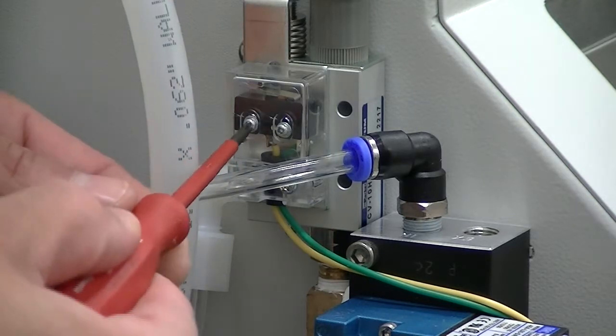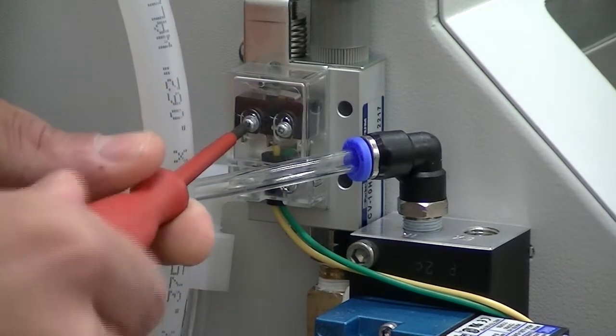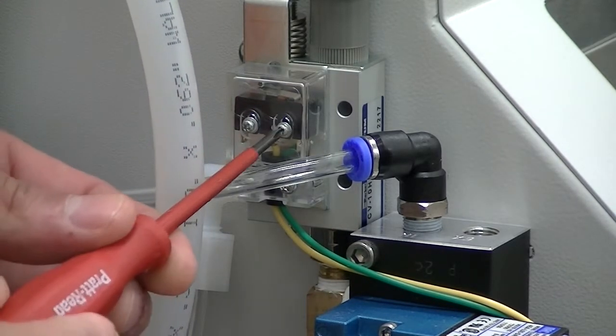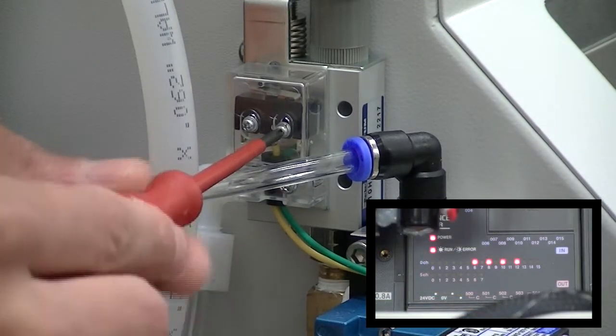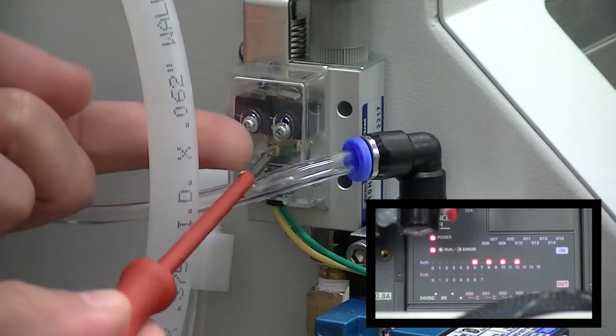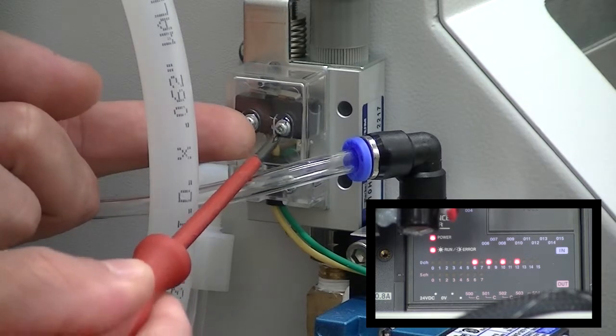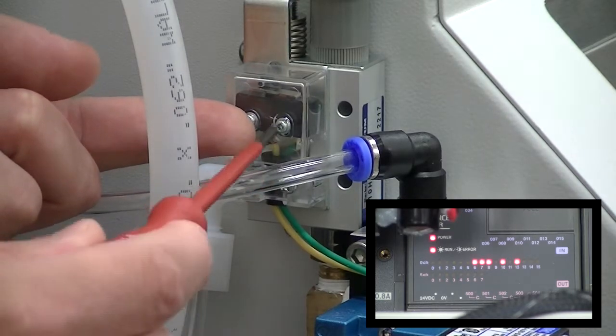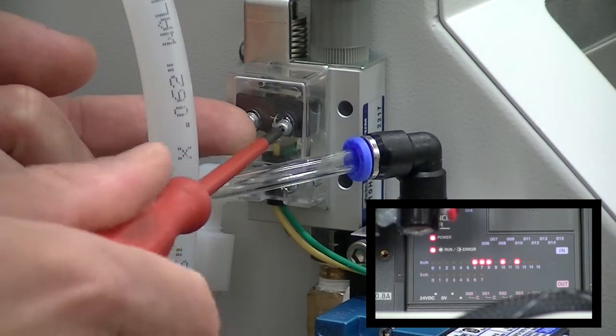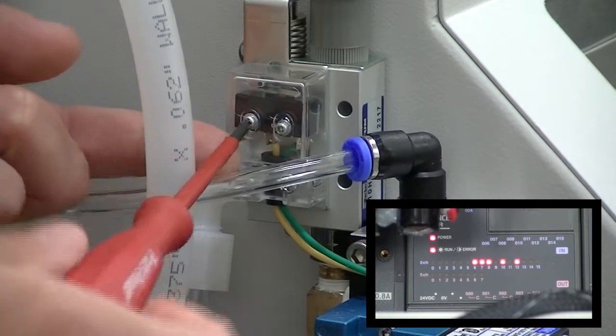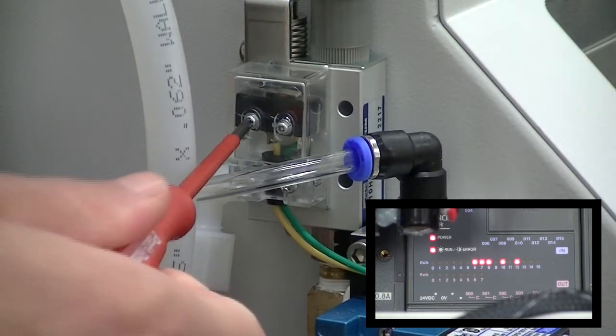Loosen. Do not remove the 2 small screws on side of transducer. Using screws, move internal micro switch till 7 light is lit on zero channel. Once 7 light is lit, tighten the 2 small screws to lock into position.